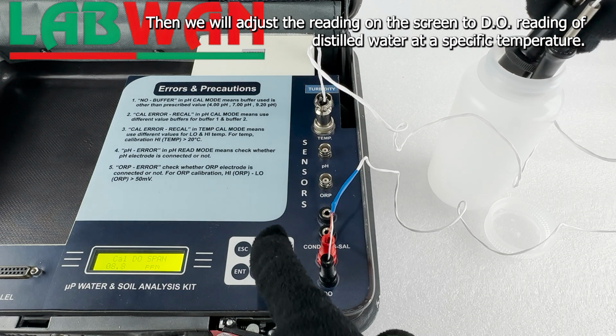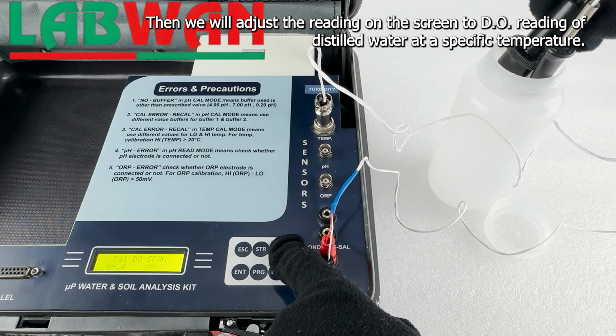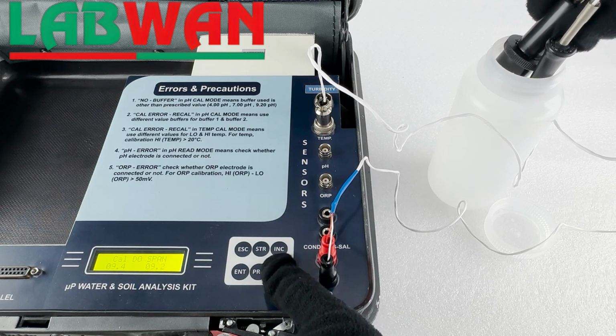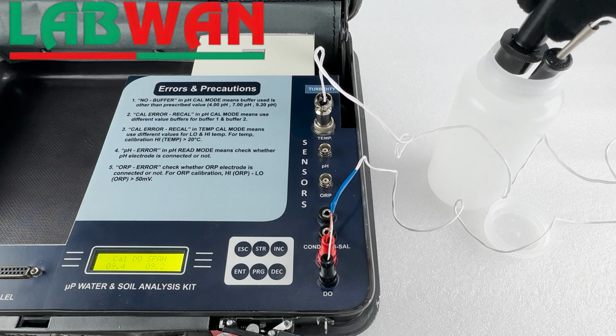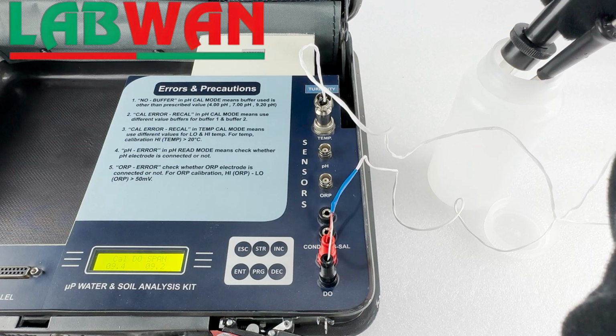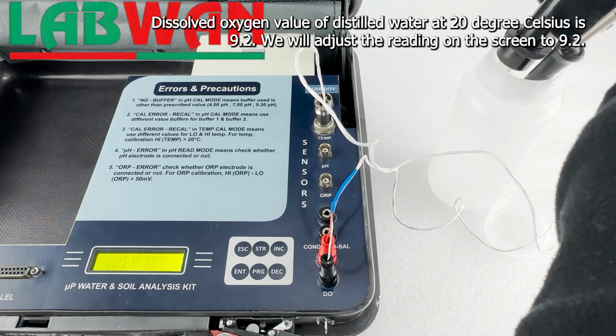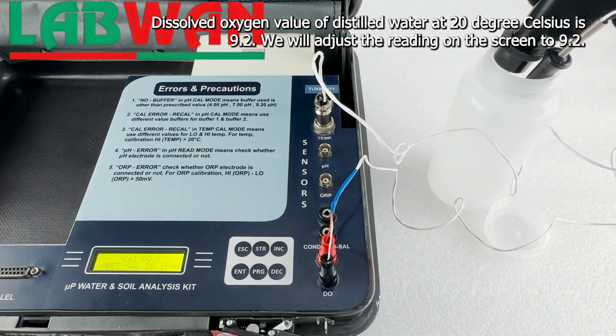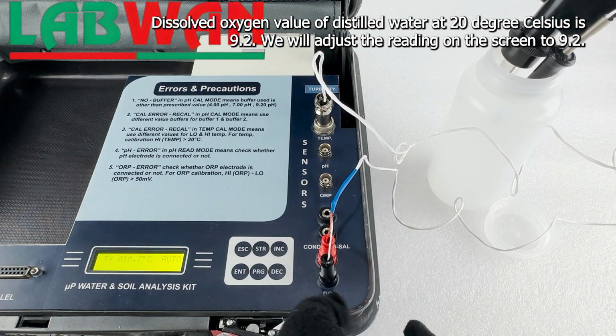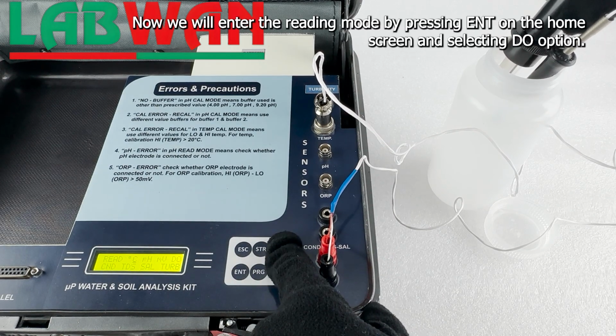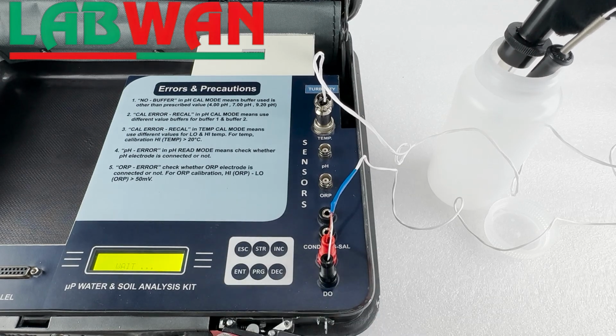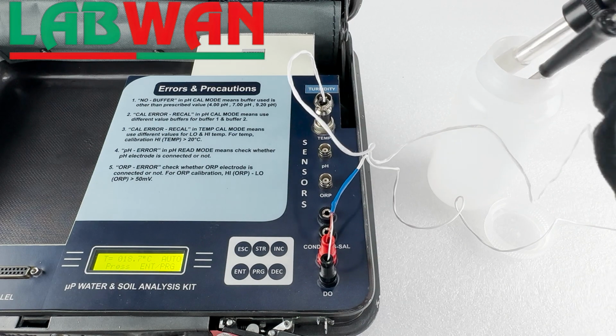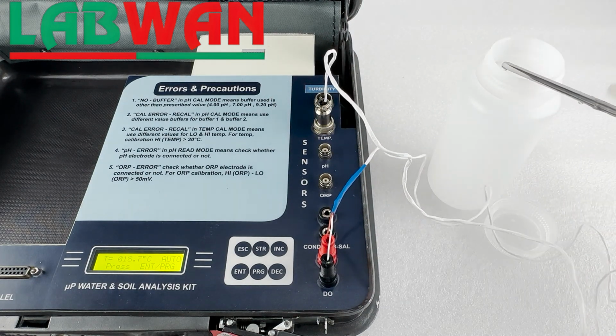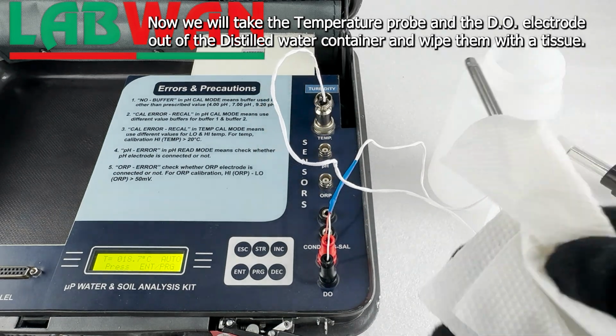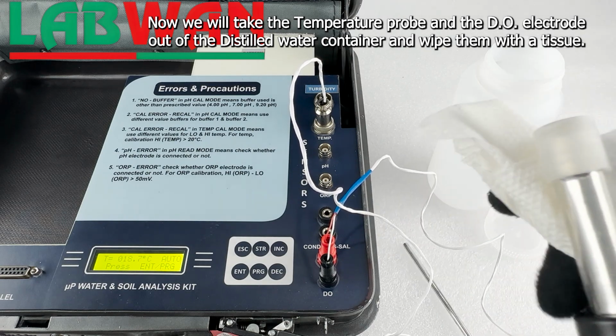Then we will adjust the reading on the screen to DO reading of distilled water at a specific temperature. Dissolved oxygen value of distilled water at 20 degrees Celsius is 9.2. We will adjust the reading on the screen to 9.2. Now we will enter the reading mode by pressing ENT on the home screen and selecting DO option. Now we will take the temperature probe and the DO electrode out of the distilled water container, and wipe them with a tissue.